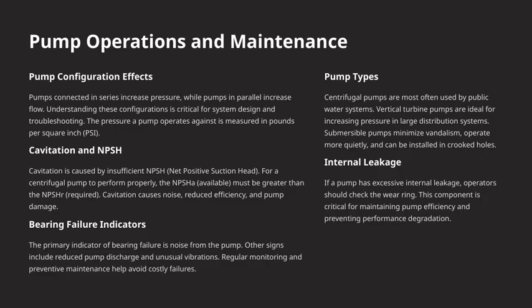When it comes to pump types, centrifugal pumps are most frequently used in public water systems because they're reliable and versatile. Vertical turbine pumps are excellent for boosting pressure in large distribution networks, and submersible pumps offer benefits like minimizing vandalism, operating quietly, and fitting into crooked or tight spaces.